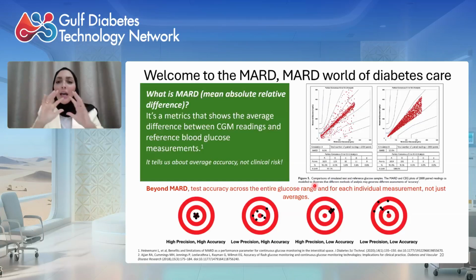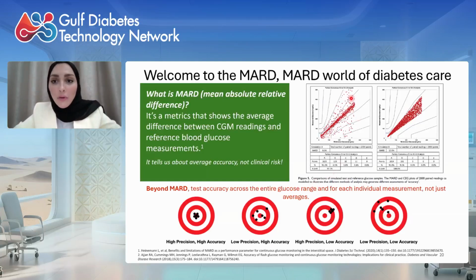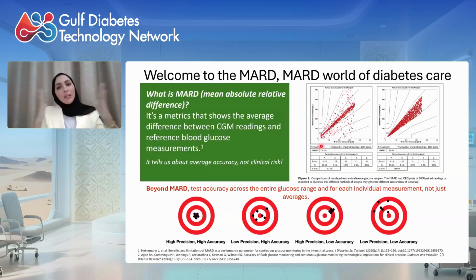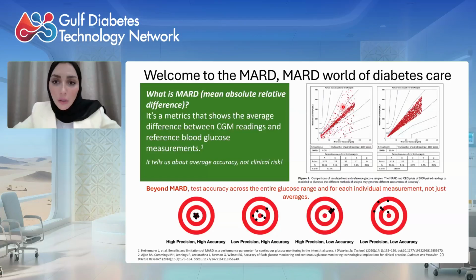However, MARD is giving us an average overview of the glucose accuracy. It does not test for the excursions. It does not test for the outliers. It doesn't test for the sensor error. It doesn't include all the readings in highs and lows. So, showing you this graph in simulation A, when they tested the MARD without looking at the outliers, it showed 8%. However, when they adjusted for the outliers, when they adjusted for the error, the MARD increased from 8 to 12. So yes, MARD might tell us about the average accuracy, but it won't tell us about clinical risk and outliers or the dangerous errors, especially with highs and lows.